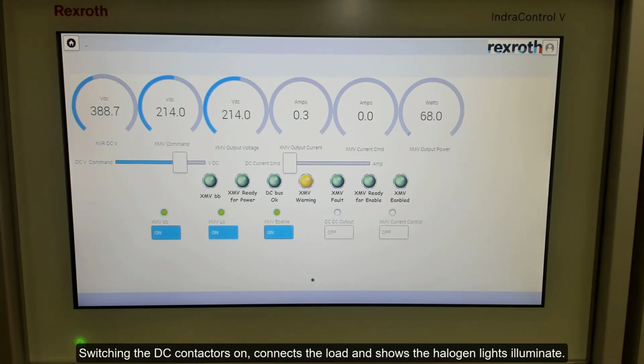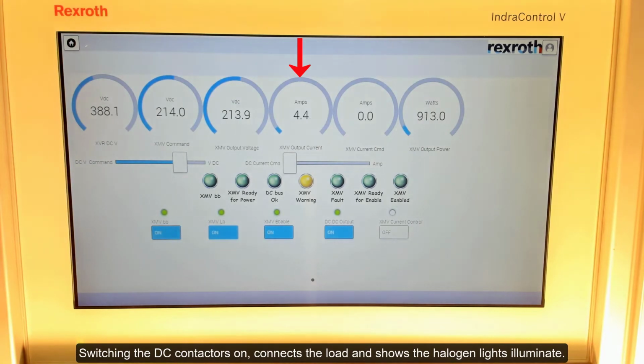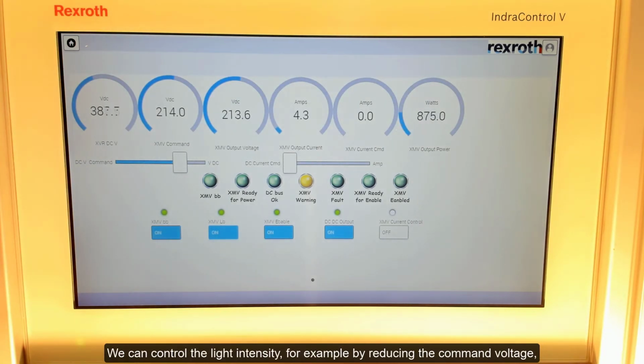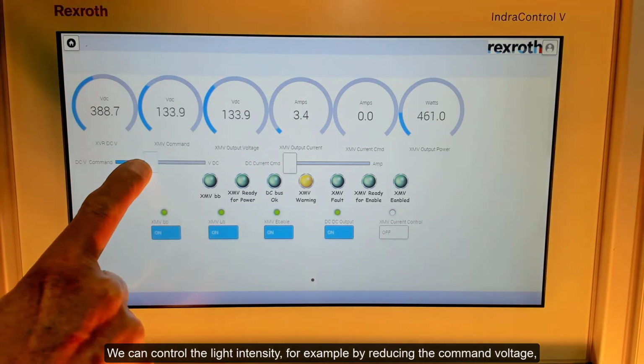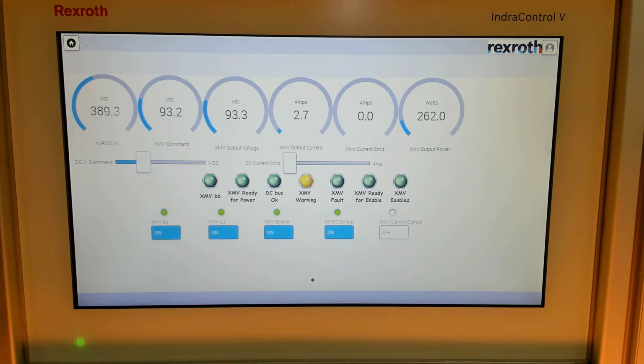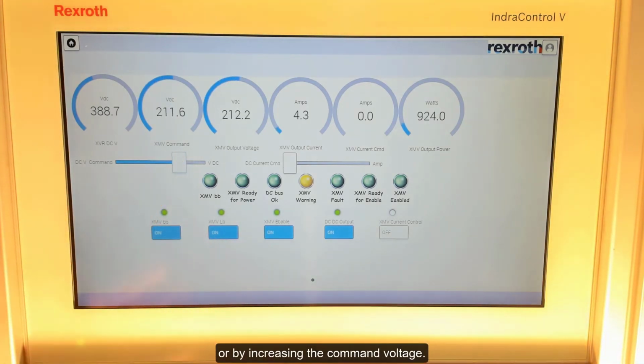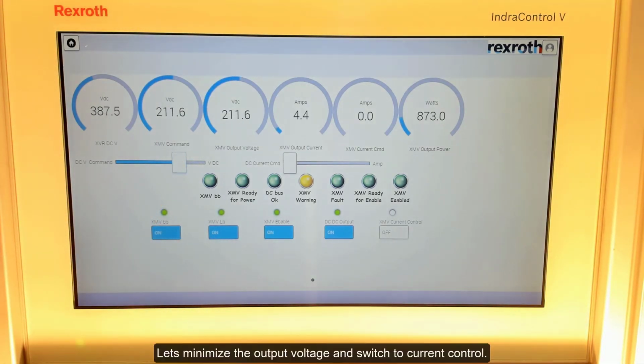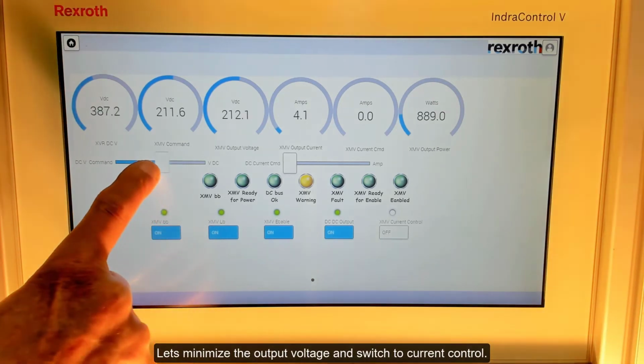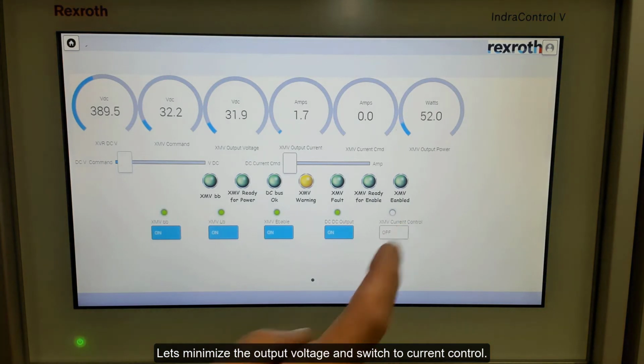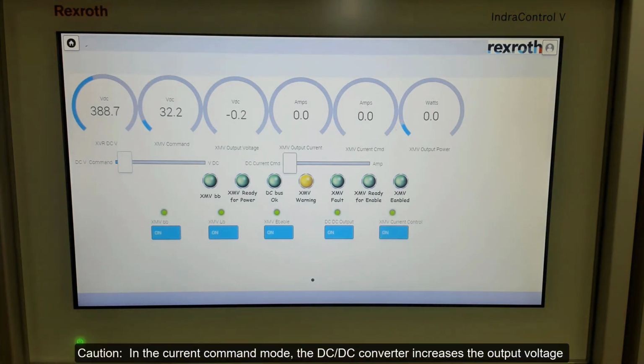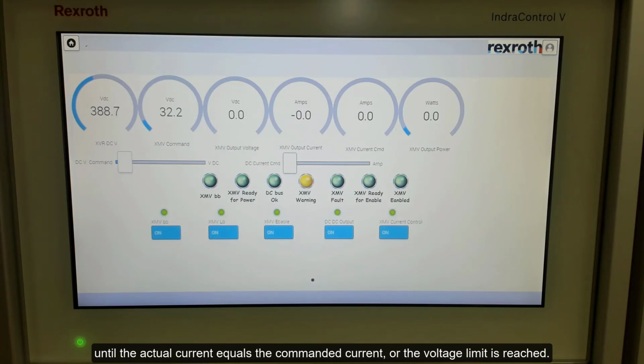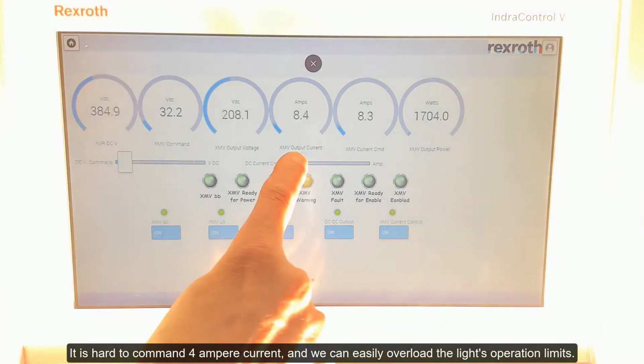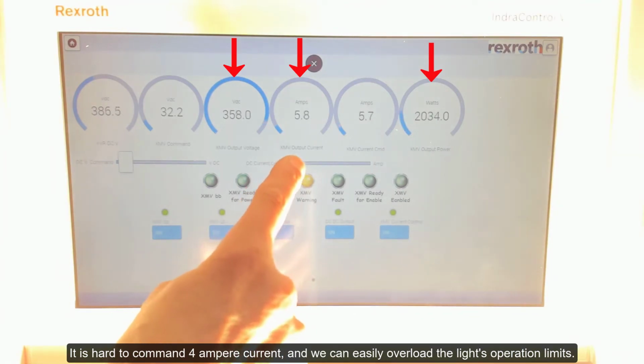Switching the DC contactors on, connects the load and shows the halogen lights illuminate. We can control the light intensity, for example by reducing the command voltage, or by increasing the command voltage. Let's minimize the output voltage and switch to current control. Caution: in the current command mode, the DC-DC converter increases the output voltage until the actual current equals the commanded current, or the voltage limit is reached. It is hard to command 4 ampere current, and we can easily overload the light's operation limits.